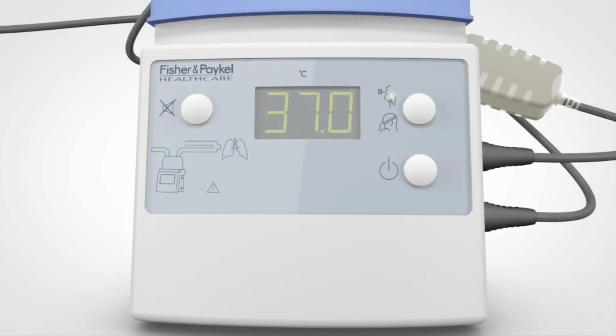Setup indicators. Temperature probe alarm. Check that the temperature probe is connected to the humidifier. Chamber probe alarm. Check the chamber probe. Ensure it is free from water or debris and ensure it is fully inserted. Airway probe alarm. Check the airway probe. Ensure it is free from water or debris and ensure it is fully inserted.